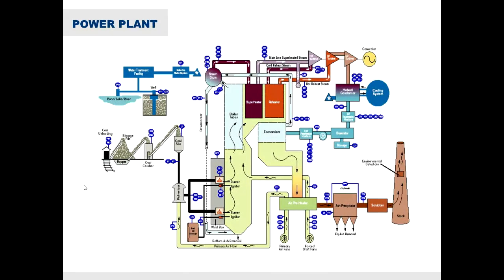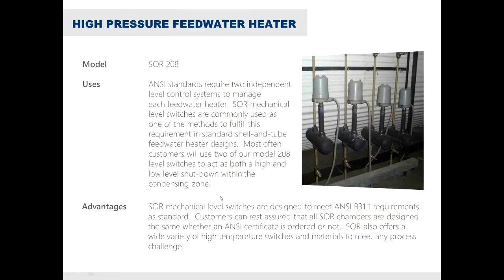One of the biggest applications is power plant applications — whether coal-fired, natural gas, or concentrated solar power plants. You're going to see level switches inside of those power plants; there's no way around it. Some of those applications include high-pressure feedwater heaters, which are among the most high-pressure, high-temperature applications you can get. Our 108/208 products handle those, going upwards of 1,200 degrees Fahrenheit and high pressures as well.